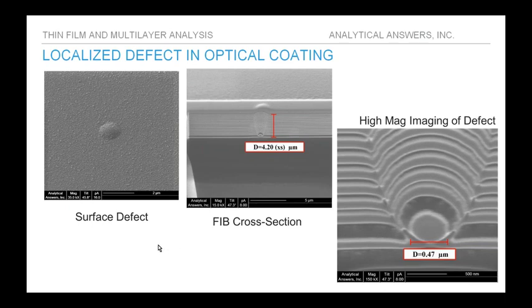The FIB provides very high-resolution imaging that we can use to look for localized defects. An example in an optical coating shows a defect seen on the surface as a roughly micron-sized dome. We can precisely cross-section this with the FIB after locating it, and we can see that the genesis of this defect is actually a buried particle very near the beginning of the multilayer stack used in this optical coating — a particle on the order of half a micron in dimension.